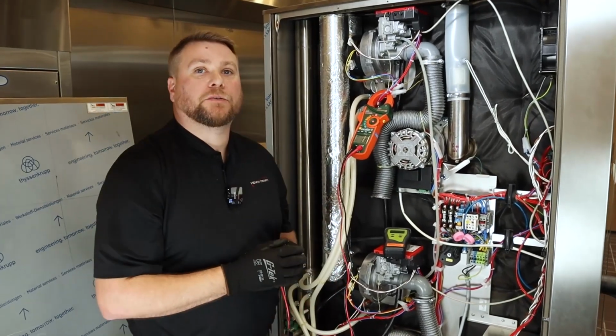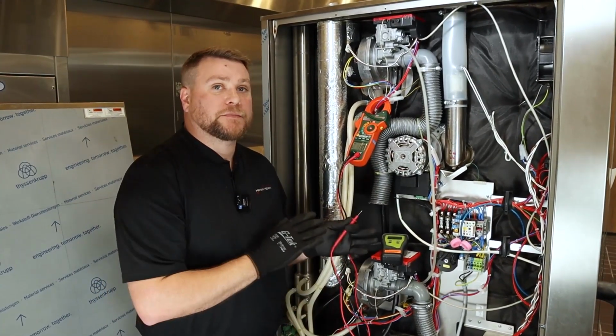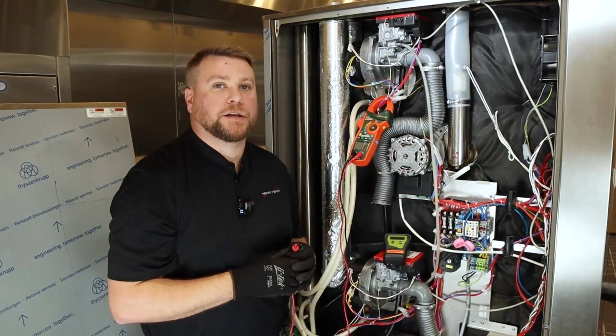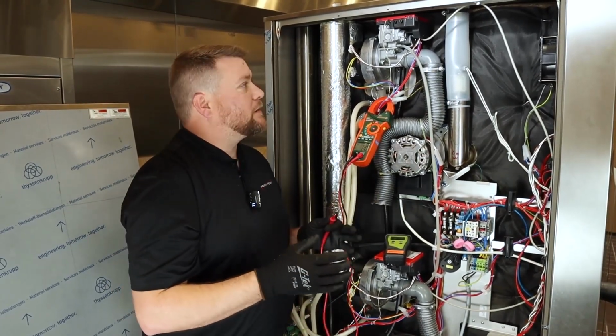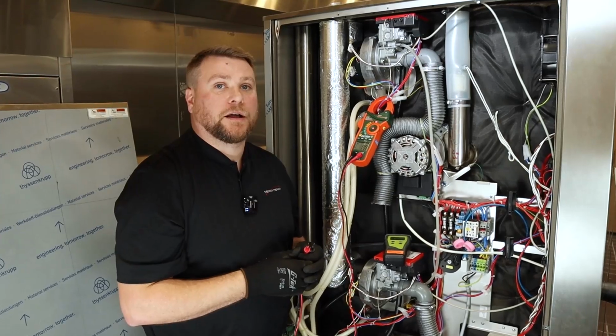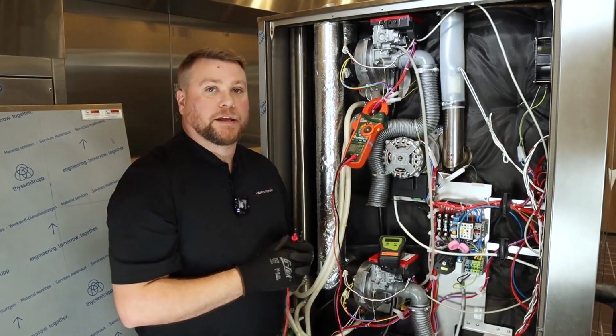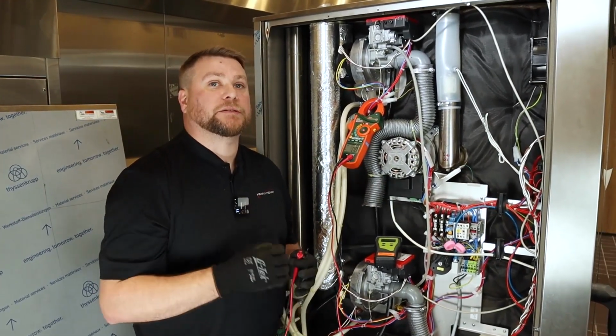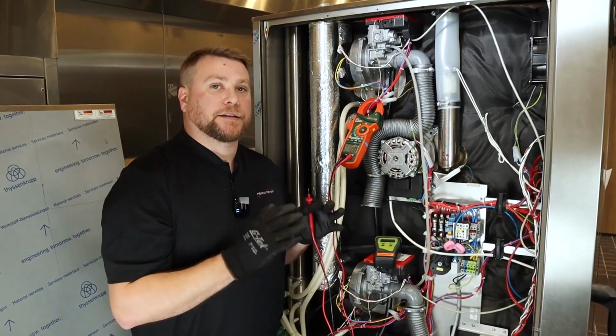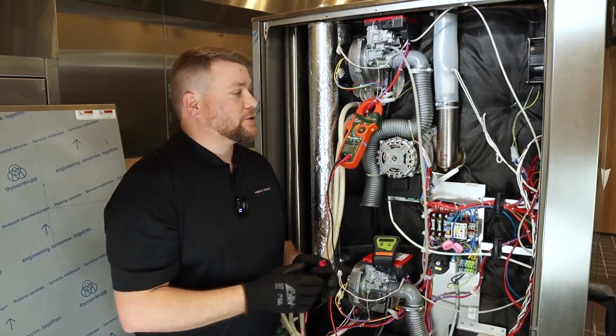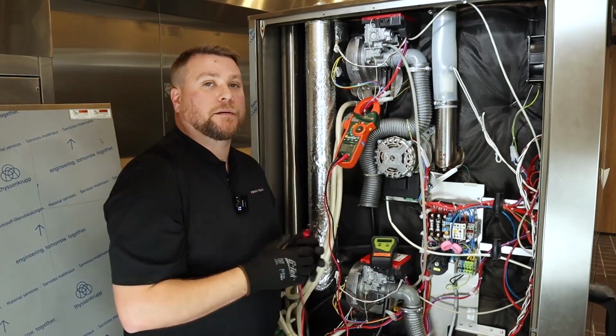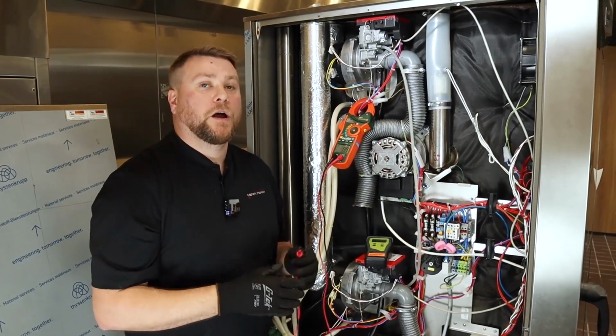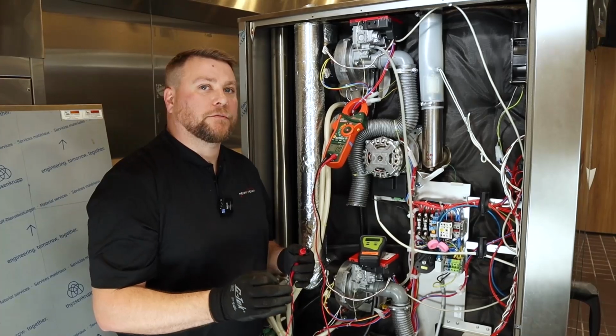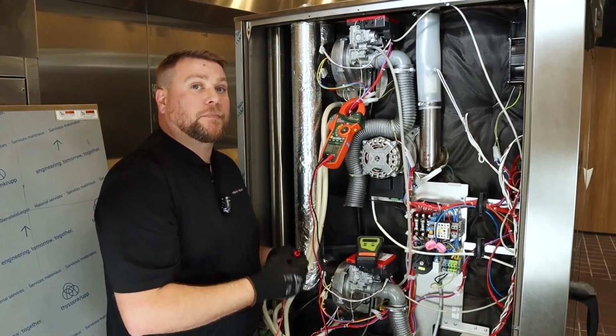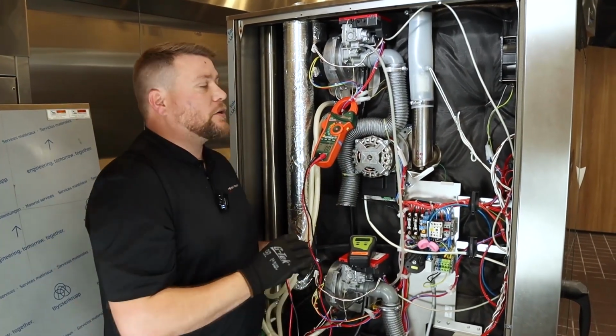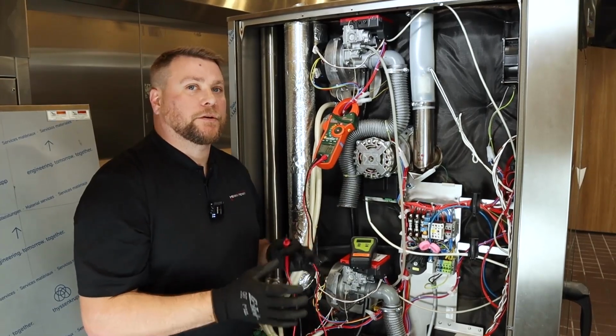Now, what I'm getting ready to do here is check flame sense and also my gas pressure reading at the same time. The reason I like to do that is because I'm going to start the unit up for a cook cycle and I can check my gas pressure. I want to check dynamic gas pressure, and that's very important. Dynamic gas pressure is when this oven and other pieces of equipment inside the store are running at the same time. And what we're looking for there is the actual volume, not necessarily the pressure. So that gives us a little bit more of a story of what's going on there.